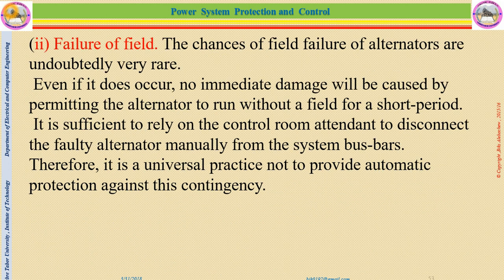The second failure of alternator is failure of field. The chances of field failure of alternators are undoubtedly very rare. Even if it does occur, no immediate damage will be caused by permitting the alternator to run without a field for a short period of time. So it is sufficient to rely on the control room attendant to disconnect the faulty generator manually from the system bus. So for failure of field also, there is no need of automatic protection against this fault.